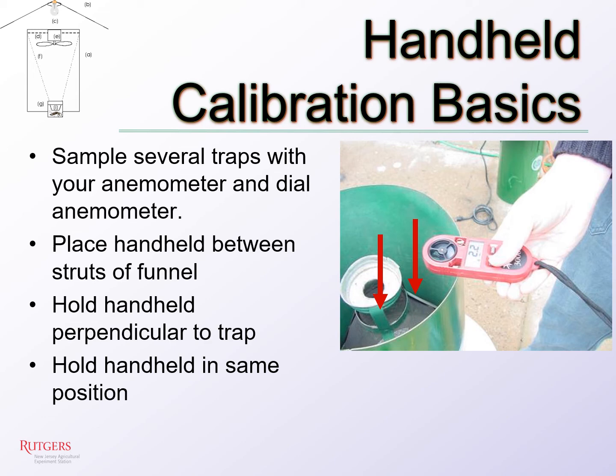Make sure you place your anemometer perpendicular to the trap and that your fan is fully inside the trap. This is the position you will want to use for your handheld in the future. Take the reading when the reading is constant. Remember, this is an instantaneous reading rather than a cumulative one as with the dial anemometer. Do 3 readings from at least 3 traps. You can also do single readings from each anemometer with at least 5 traps. The more traps you read from, the more precise your line will be.